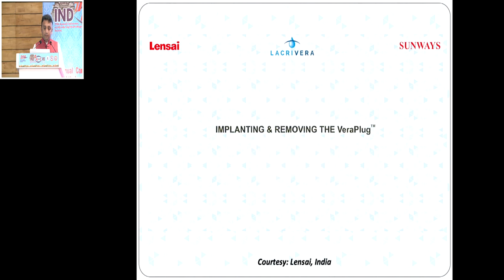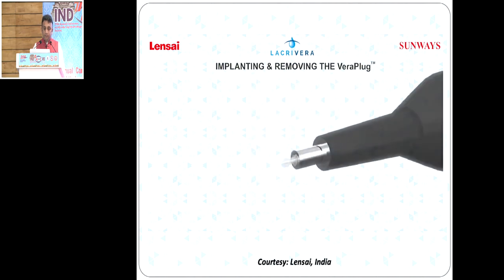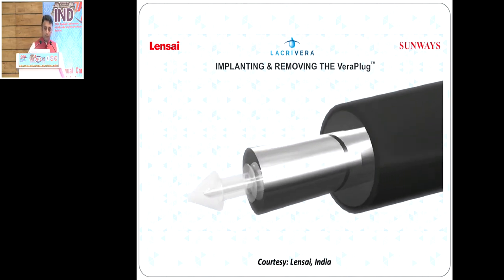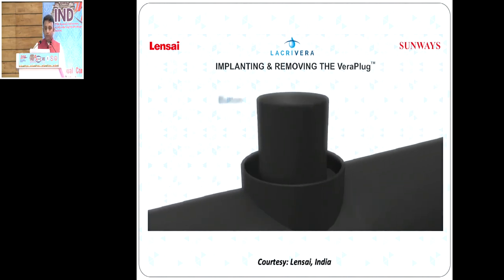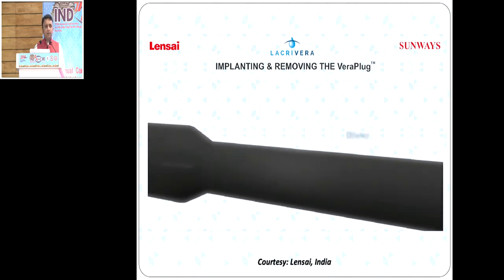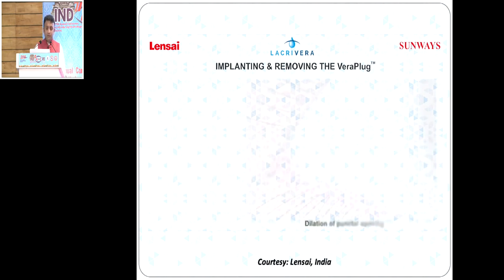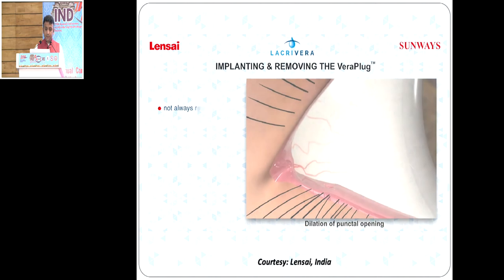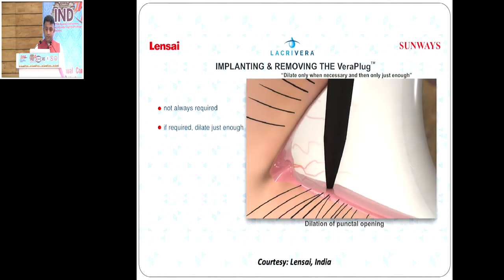Implanting and removing the Vera plug. So there are multiple such devices available in the US market and other markets. Assess the punctal opening before implanting the plug. However, if dilation is required, it is necessary to dilate it just enough to insert the Vera plug into the opening. Excessive dilation may cause the punctal annulus to be overly stretched, potentially increasing the risk of punctal migration or extrusion.